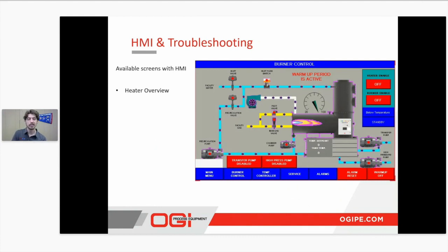So looking at the heater overview screen, whenever your tech comes for the startup, on here you'll go ahead and enable the heater, enable the burner up in that top right-hand section. If you want the QuikWater to not pump out water until it's met your specified temperature, say you want it to be 180, and you can't have cold water on your cleanup floor, you'll enable our warm-up mode on the bottom right-hand corner. This will make sure that the water is discharging at that 180 degrees. That way you don't have any cold water coming out of the nozzle heads on your spray floor.